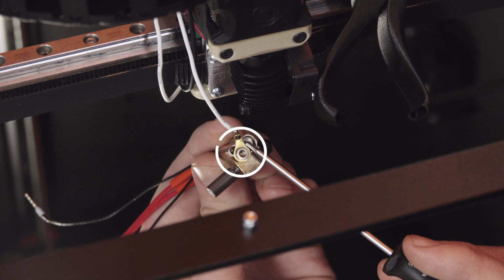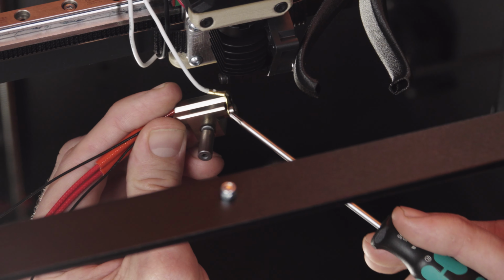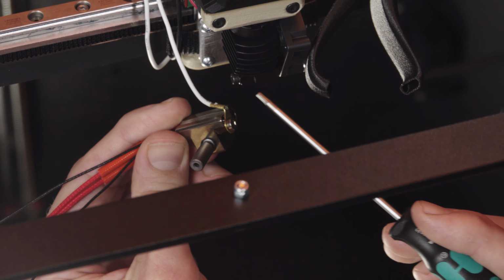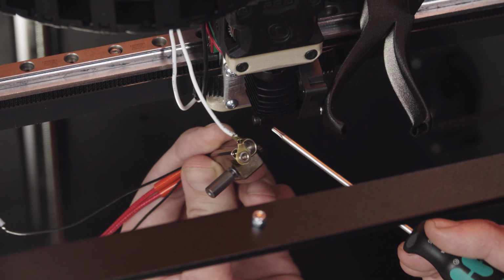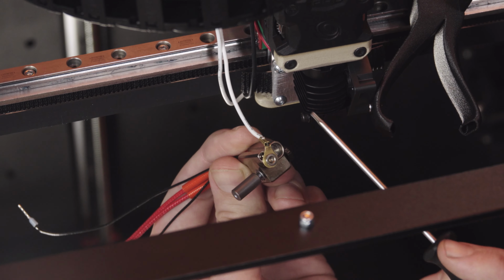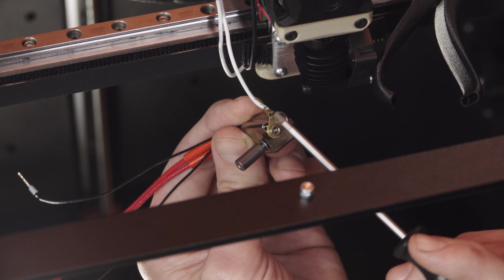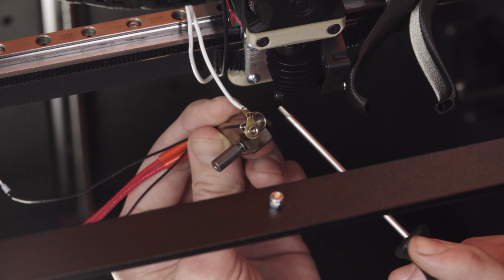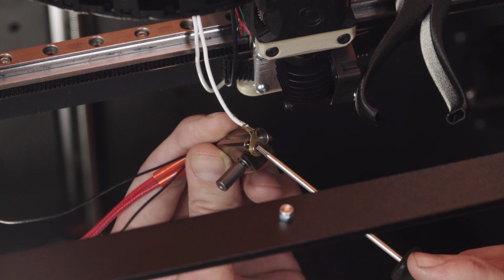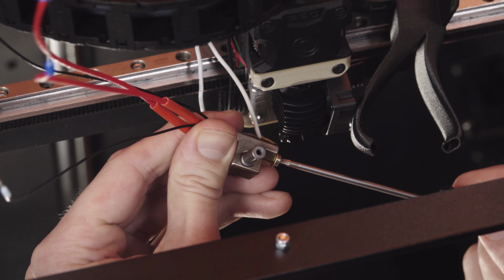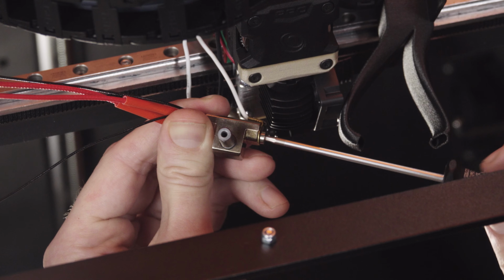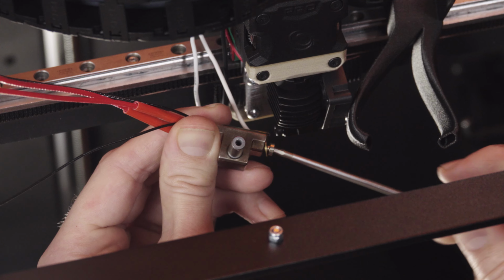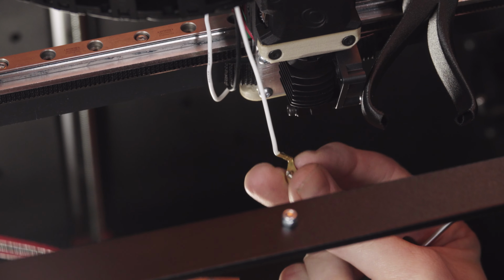You'll see right here, it's on an angled bracket, sort of down at an angle. This is really important: when you reinstall this, it needs to stay at that angle, because that prevents it from hitting any other metal in the area. If it does touch metal, it's going to mess with the calibration. So remember how this is, and when you put it back, make sure it's maintaining that angle. To remove it, we just unscrew this one screw, and there we go.